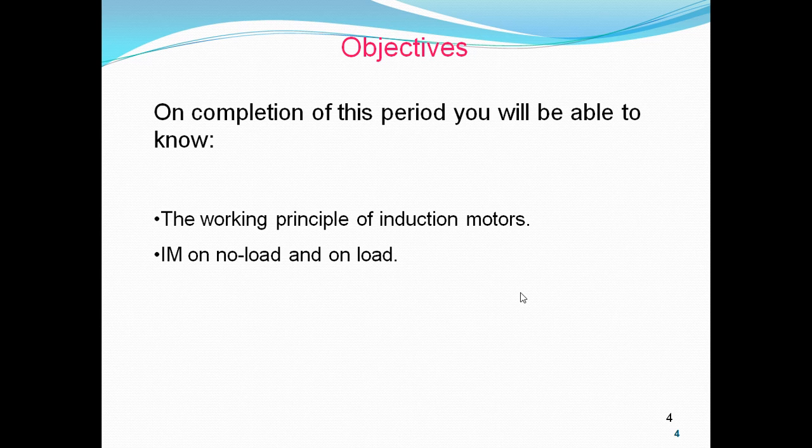Under normal running conditions, the slip rings are short circuited; only at the time of starting is external resistance connected. So this arrangement makes it possible to add external resistance to each phase of the rotor during the starting period, to increase the starting torque.